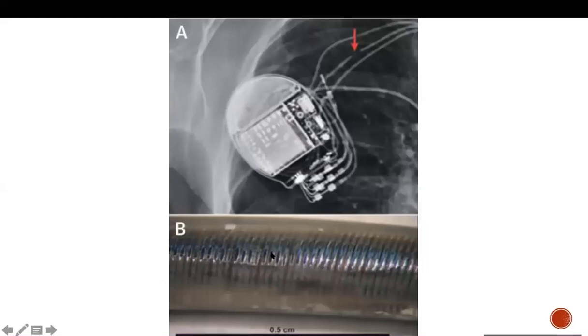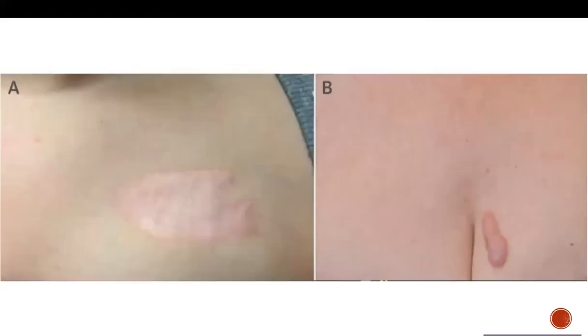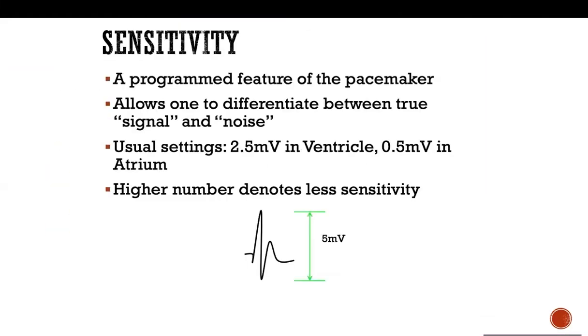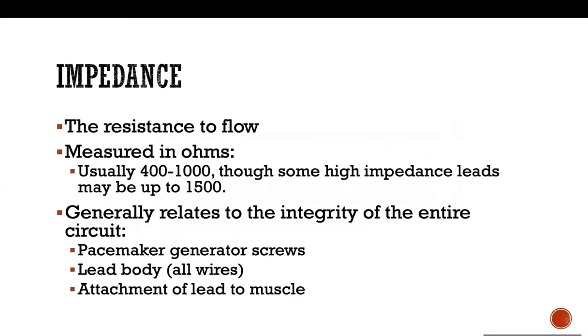over here. So this one we call insulation break. Usually there is very low impedance. And over here we said, the pacemaker generator screws. So if it's not screwed properly, attached properly to the pacemaker or the ICD, it is going to give you a low impedance. And attachment to the muscle. So if it's dislodged, the same thing, you're not hitting muscle, so there is no resistance. So the impedance is low.